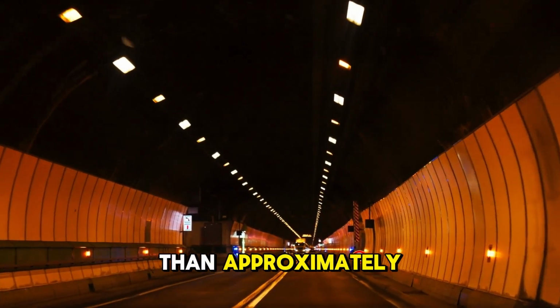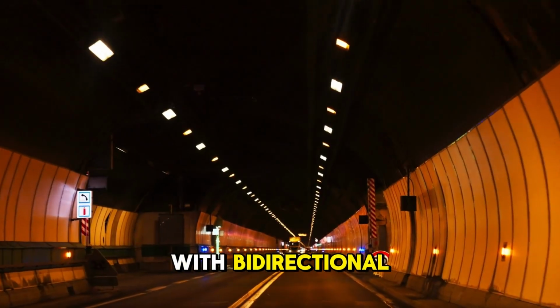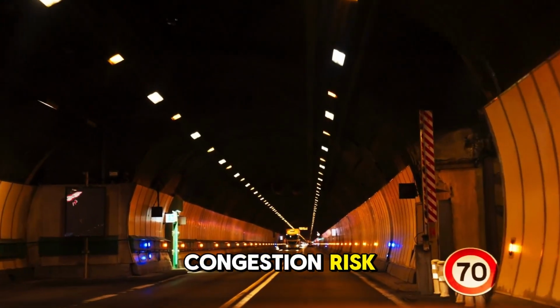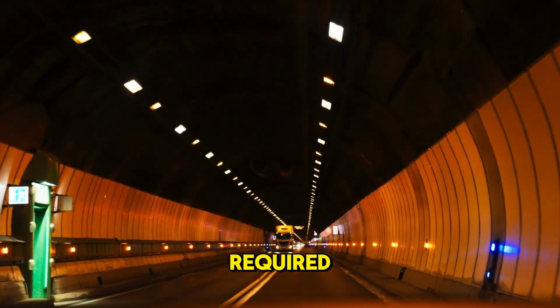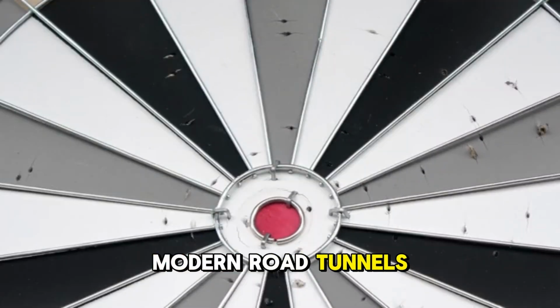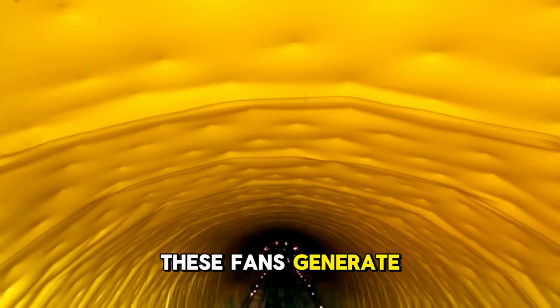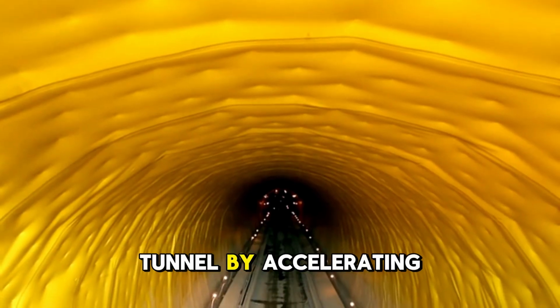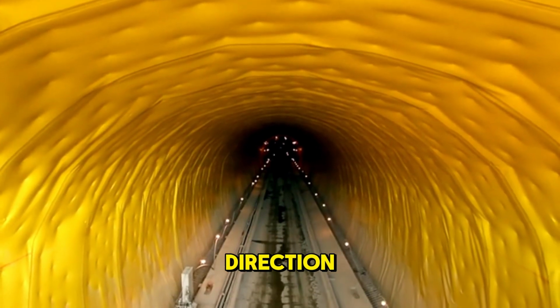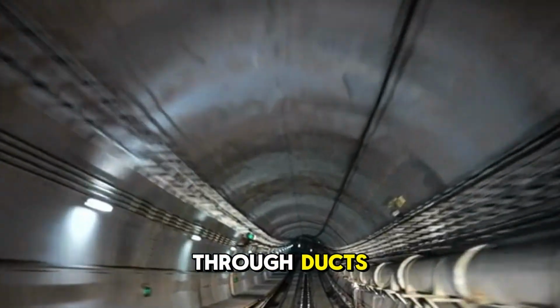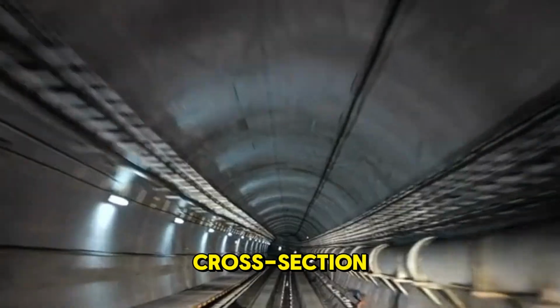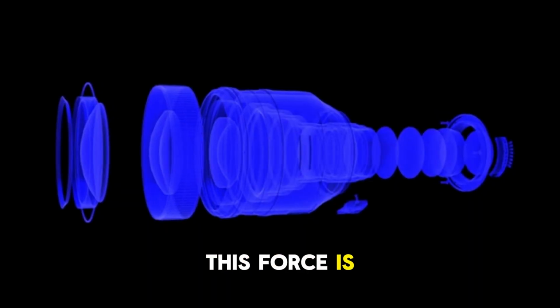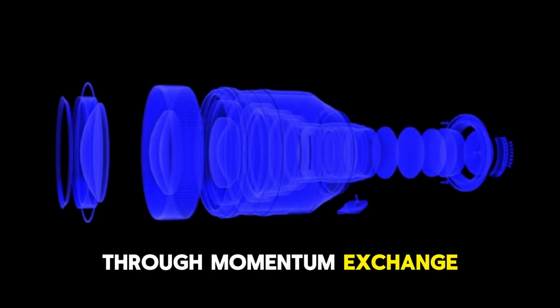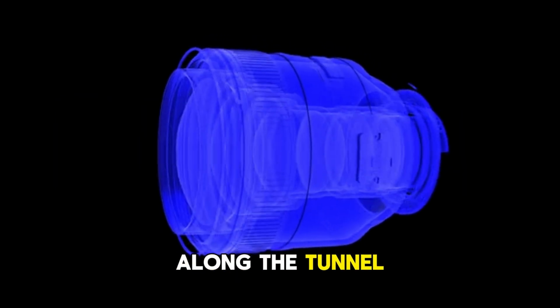For tunnels longer than approximately 400 meters, or any tunnel with bidirectional traffic or significant congestion risk, mechanical ventilation is required. The dominant system used in modern road tunnels is jet fan ventilation, a longitudinal system in which axial fans are mounted in the tunnel ceiling. These fans generate a longitudinal airflow along the tunnel by accelerating the air mass in the desired direction. Jet fans do not move air through ducts. They operate in the open tunnel cross-section, creating a thrust force. This force is transmitted to the tunnel air through momentum exchange, building up a bulk airflow along the tunnel length.